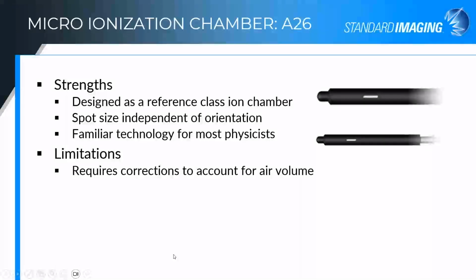Strengths of the A26 then, as I mentioned, all of these detectors really have strengths and limitations. The A26 was designed to be that reference class type ion chamber, to have a spot size that was independent of orientation, a nice spherical spot size. And ion chambers really are familiar technology for physicists. We're comfortable working with ion chambers. We kind of understand where they can go wrong, and how to interpret the measurements. So it's a comfortable space to work in.